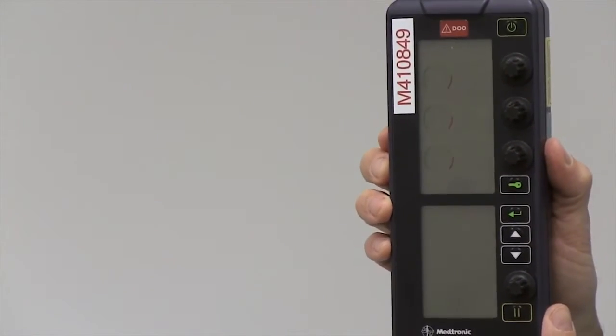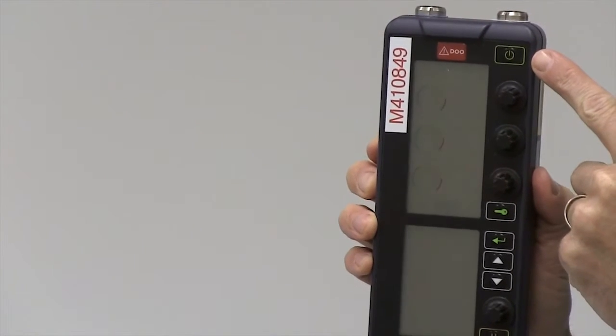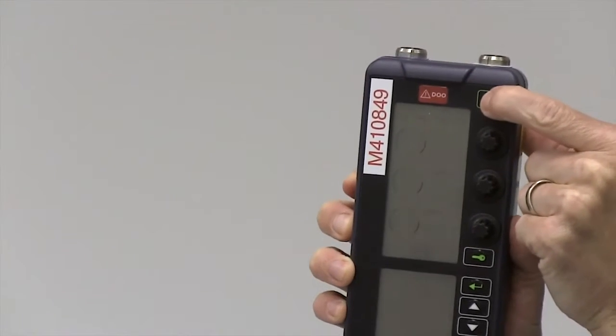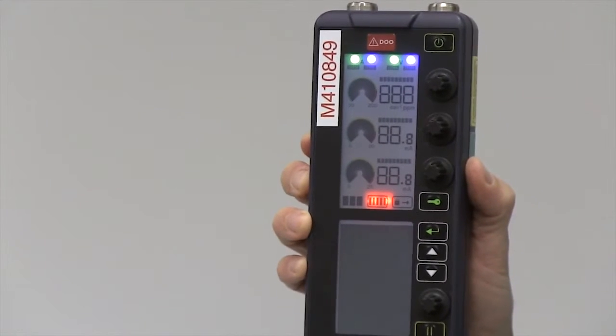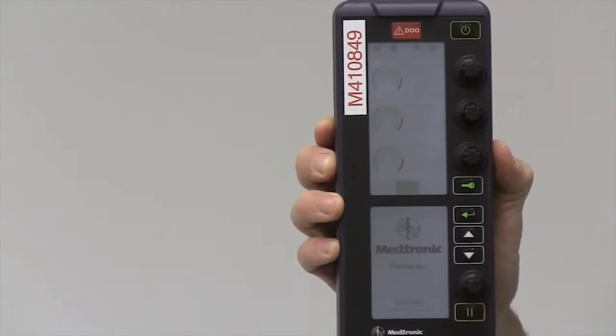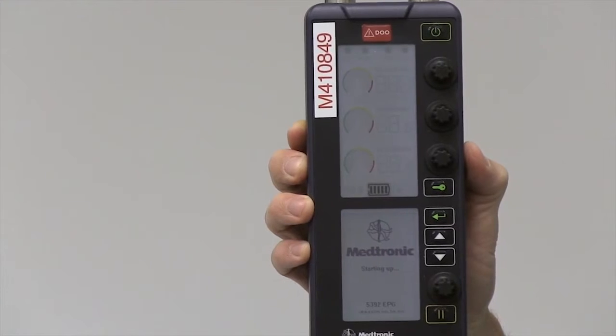To turn on the pacemaker generator, in the top right-hand corner, there is a green button. You need to press and hold that button until the lights start turning on the generator. It takes a couple moments for it to boot up.